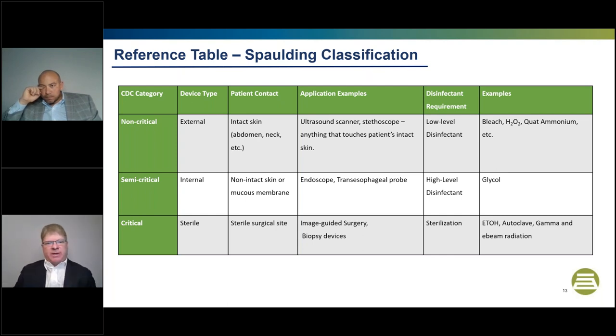Lastly, and most critically, pun intended, is the sterile category, which is going to operate in a sterile field, such as a surgical device or biopsy device, or even image-guided surgery. That's going to require sterilization, and that could be ambient temperature gas, ethylene oxide, autoclave steam - which Raf just mentioned - or gamma and E-beam radiation, which, as a teaser, we have another case study at the end of the talk that talks about that.